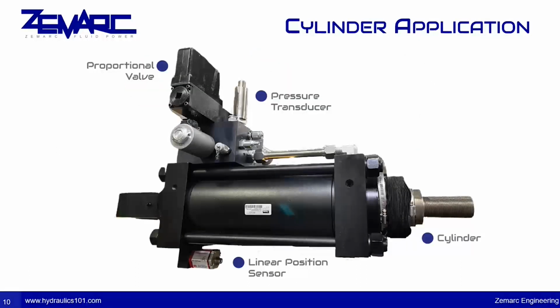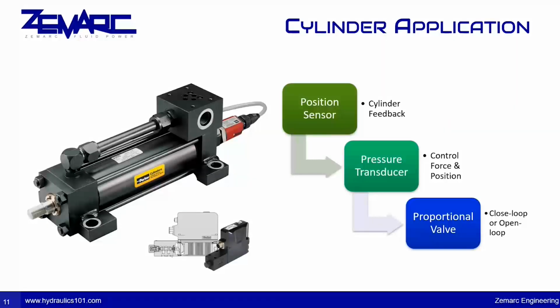Now, in cylinder applications, common sensors include stuff like proportional valves, pressure transducers, and built-in linear position sensors inside the proportional valve. And in cylinder applications, feedback is important for accurate control and monitoring of hydraulic or pneumatic systems. Here are some more details on the types of important feedback. You have your position sensor, and the linear position sensor can be used to measure the position of a cylinder's piston, or other moving parts. And this information can be used to control the cylinder's movement and position, or provide feedback on the performance.